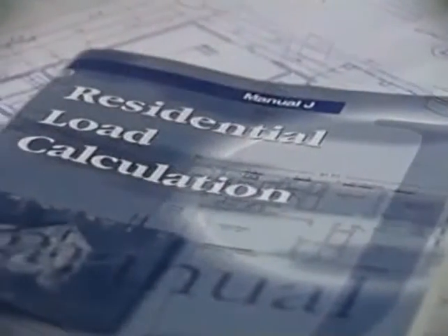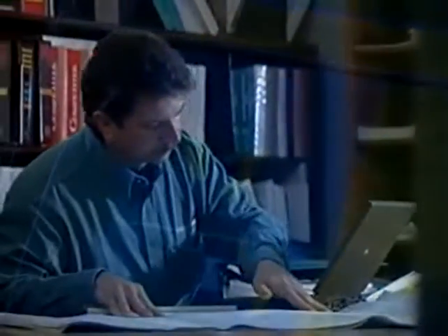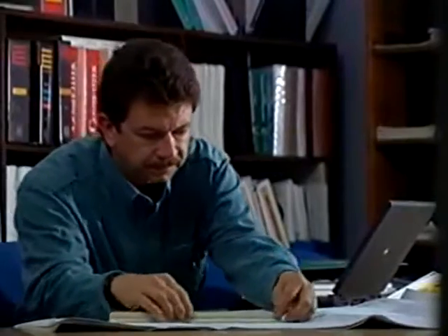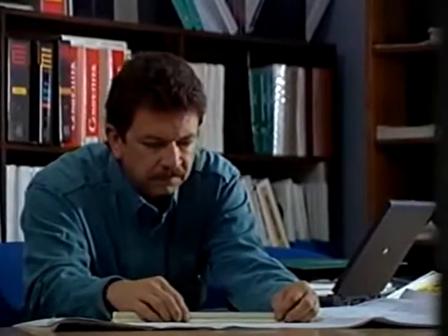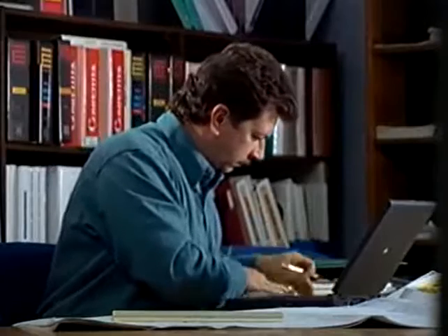Determining how much air should be delivered in each room and returned back to the air cooler is an essential part of the equation. As a contractor, you can use a number of tools to design air distribution, including ACCA Manuals J and D and computer programs based on the ACCA design standards. Without a plan, your air distribution system will not deliver comfort. If we're just doing this on a random basis, just pulling ducts from a rule of thumb, it's not accounting for the fact that people live in the building and the fact of their lifestyle and their perception of comfort.